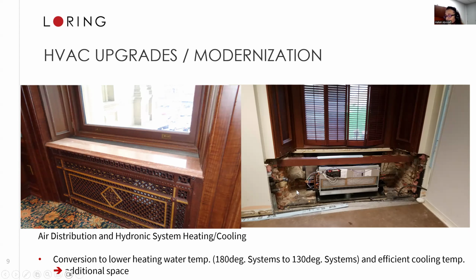If you're going through an electrification strategy using a heat pump, most often you're going to move away from 180-degree class systems—high temperature hot water heating systems—to 140 degrees, sometimes 130 or even lower. What that means is the coil or radiator housed within these enclosures now has to be larger to accommodate a lower temperature.